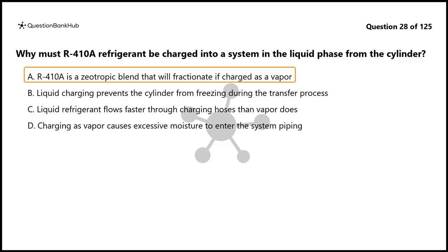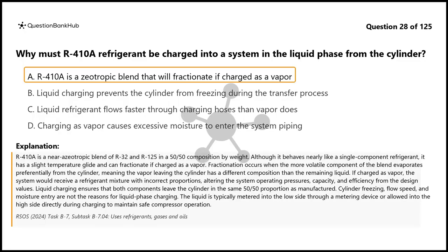The correct answer is A. R410A is a near-azeotropic blend of R32 and R125 of 50/50 composition by weight. Although it behaves nearly like a single-component refrigerant, it has a slight temperature glide and can fractionate if charged as a vapor. Fractionation occurs when the more volatile component of the blend evaporates preferentially from the cylinder, meaning the vapor leaving the cylinder has a different composition than the remaining liquid.